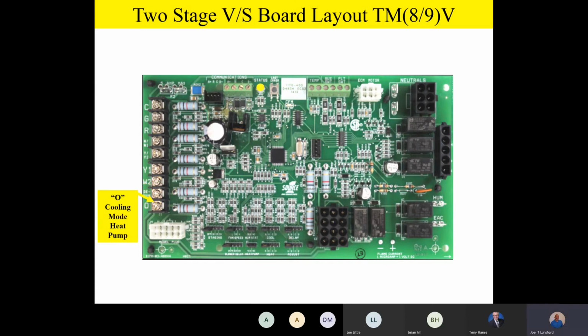Okay. Below that is an O for a cooling mode on a heat pump. This board is set up to be hooked up to a heat pump, dual fuel. Just make sure that if you do have it on a heat pump, you have to configure the board and let it know it's on a heat pump by a jumper. And we'll show you where that jumper is in a little bit, where it says heat pump or AC. So make sure if it is on a heat pump that you have the jumper set to heat pump, HP or heat pump yes, no, and then it'll be looking for that O terminal for the reversing valve on a heat pump in the cooling mode.